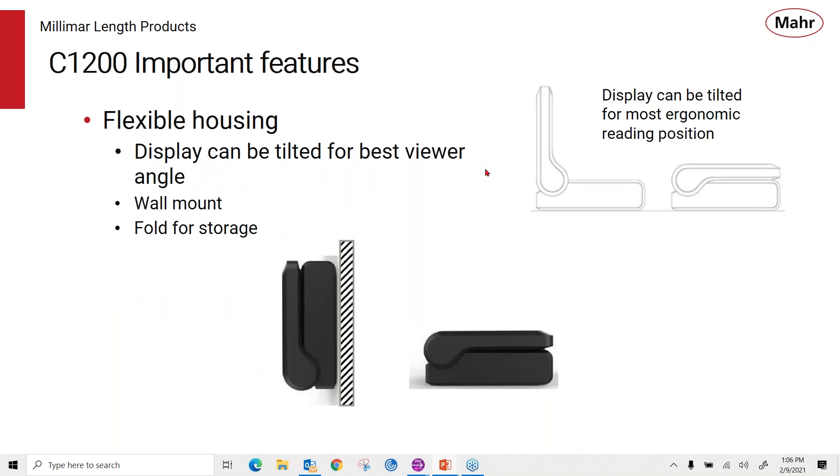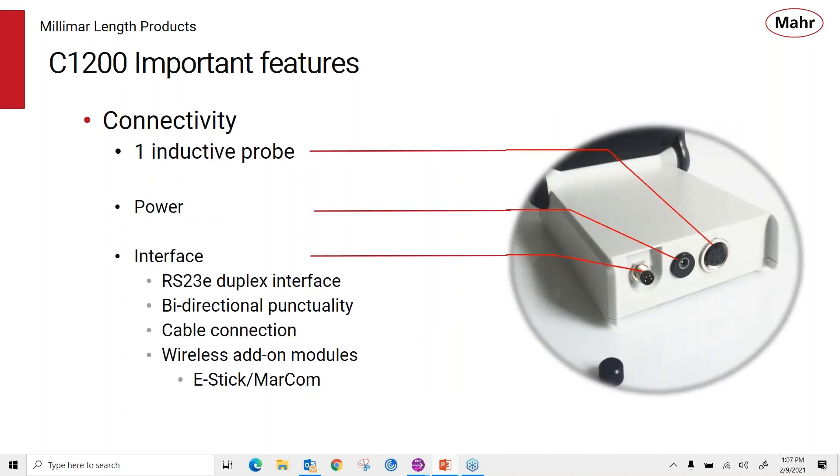With its flexible housing, the display folds up or folds down so you can angle it to the most ergonomic reading position. You can wall mount the amplifier or fold it up to store it away so it doesn't take up much room — you can put it in a drawer with the probe and it won't get damaged. On the connectivity side, in the back of the amplifier there's a connector for one inductive probe, your power connector, and one of our standard connectors for data output — an RS-232 full duplex bidirectional interface. You can use cable connections or one of Mahr's add-on wireless modules with our e-stick to take wireless data transmission into MarCom.